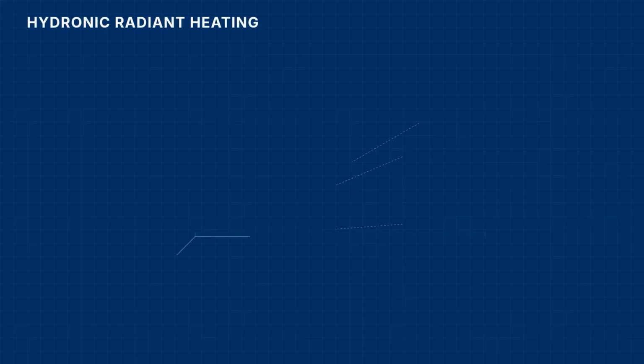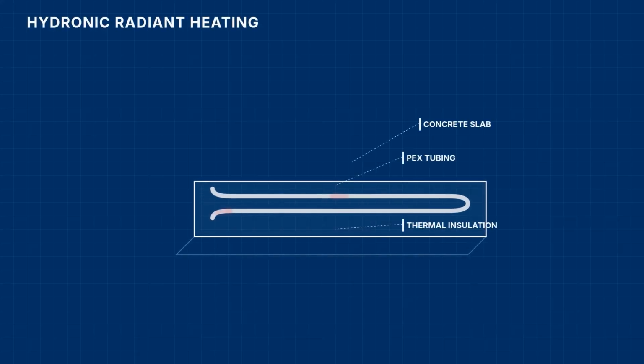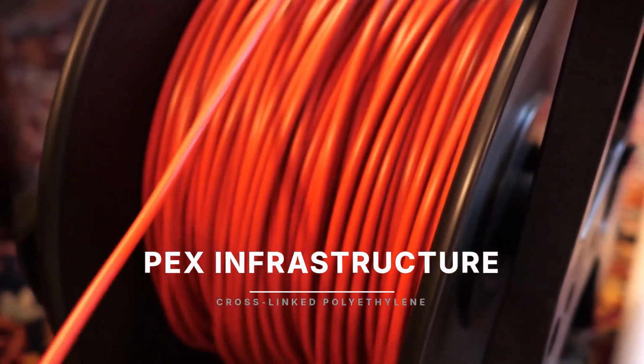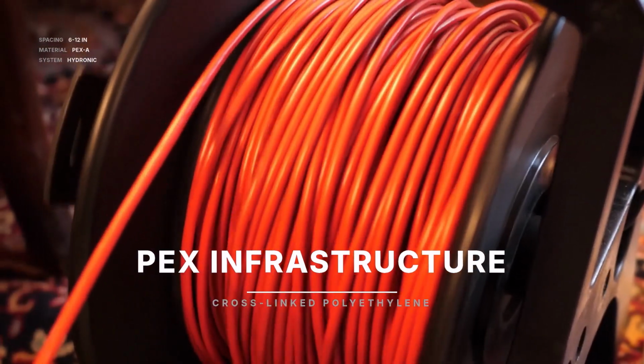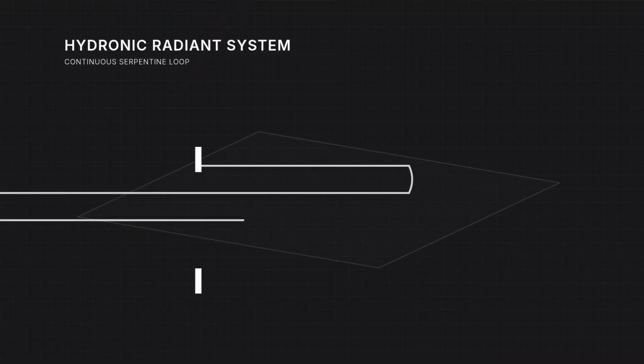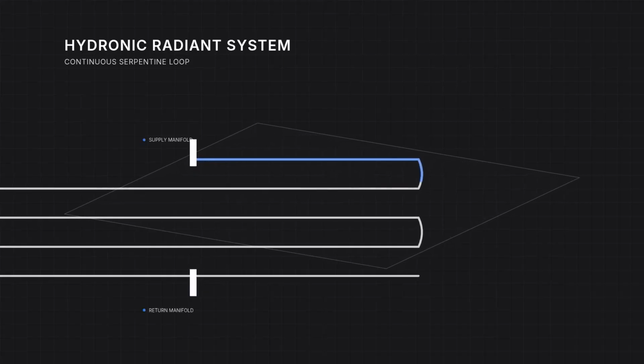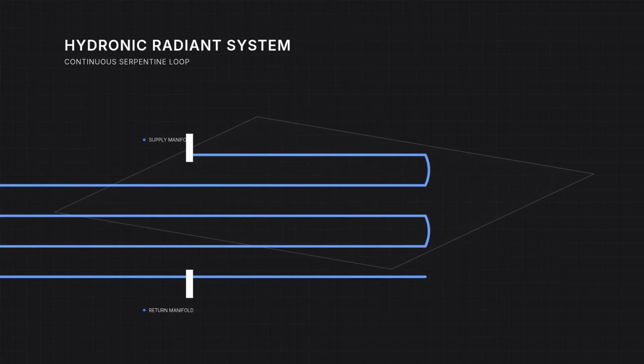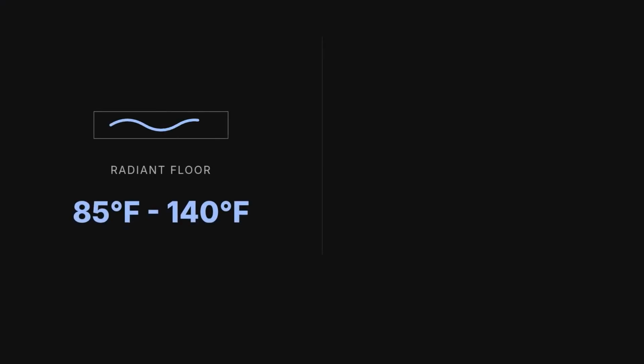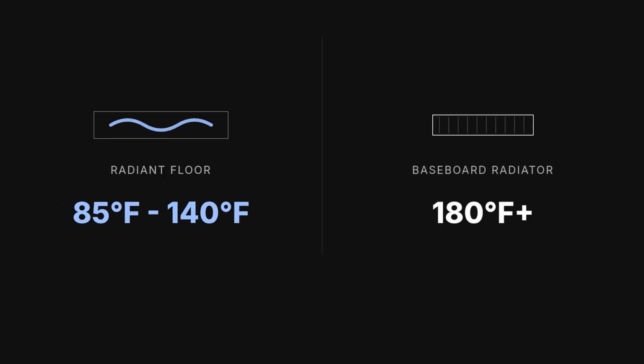The modern hydronic radiant floor heating system works through the same thermodynamic principle that warmed Roman villas. Radiant heat transfer from a large low-temperature surface to the occupants and objects in the space above it, delivered through technology that is buildable in any new project. Cross-linked polyethylene tubing, PEX, is embedded in a concrete or gypsum floor slab at a spacing of 6 to 12 inches, running in a continuous serpentine loop from a supply manifold to a return manifold. Hot water circulates through the tubing at temperatures between 85 and 140 degrees Fahrenheit, significantly cooler than the water in a conventional baseboard radiator system.